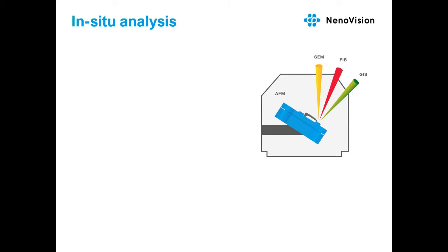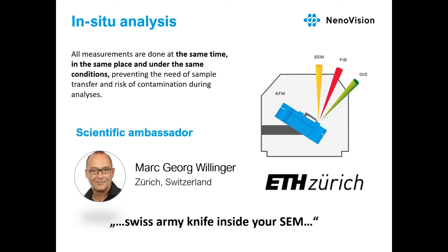The second important field is in-situ analysis. Since we integrate AFM inside the chamber, all the measurements are done at the same time, in the same place, and under the same conditions. For instance, thanks to no transfer between chambers, the sensitive samples are not contaminated by air. I'm happy to say that our ambassador for in-situ analysis is Marc Willinger from ETH Zurich, and I really like his claim that LiteScope is like a Swiss Army knife inside your SEM. So simply, the added AFM functionalities widen the possibilities inside the SEM chamber.